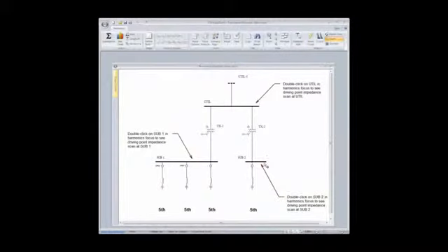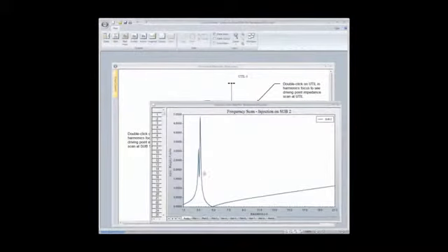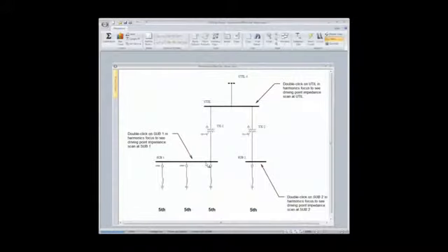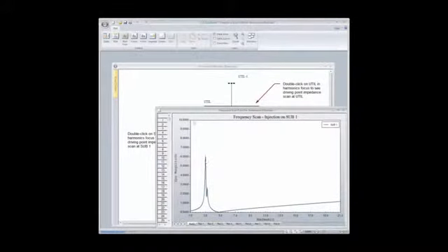We can also see, if we double-clicked on the other bus, that it would manifest slightly differently. Now, the auto scaling kind of threw this up. It makes it look like it's a lot bigger. It's basically about the same resonant peak. The other auto scale jumped up to like 10, I believe, if we look over here. Yes, see, it jumped up to a scale factor of 10. So it went a little bit above 5, but these both have about the same characteristic with a little bit of a mirror image going on.